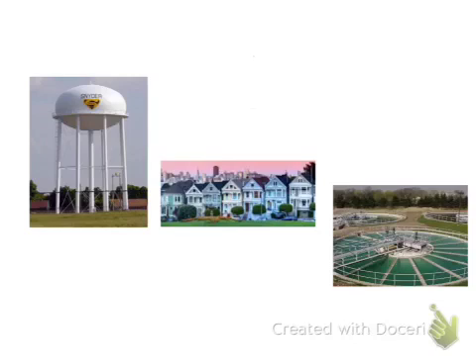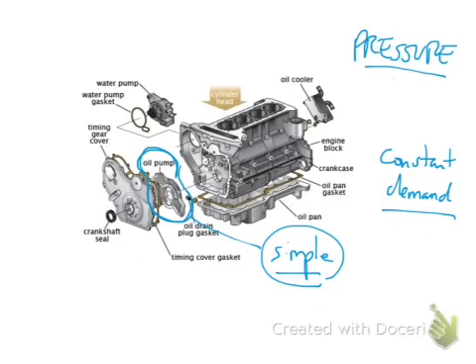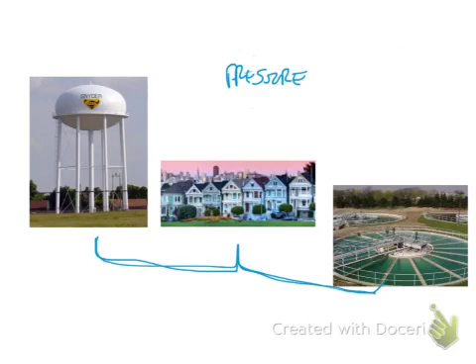So, how is a water distribution system similar to an engine? It needs to maintain pressure — the pressure has to go through all the lines. Just as something bad happens if the oil pressure drops to the engine, something bad is going to happen if the pressure drops in the water system. The water flowing through the pipes needs to be pushing out all the time, under pressure, because there might be leaks along these lines. If the water is not pushing out, water from outside — which is not clean water — might get in due to lower pressure, and it might have bacteria, a virus, or some sort of pathogen that can contaminate it.